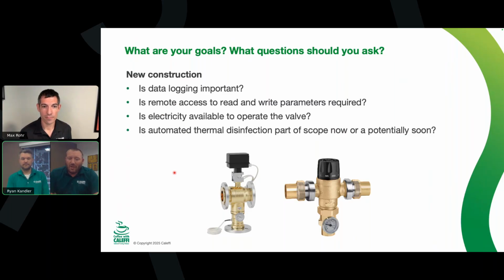Another important feature is remote access, being able to read the parameters and adjust a mixing valve. If it's hard to get at, a thermostatic mixing valve probably isn't the greatest choice. With an electric mixing valve, you can set the controller in a convenient spot and run wires to the actuator. Also, is electricity available in that mechanical room? If not, a thermostatic actuator can save you thousands of dollars by not needing an electrician.